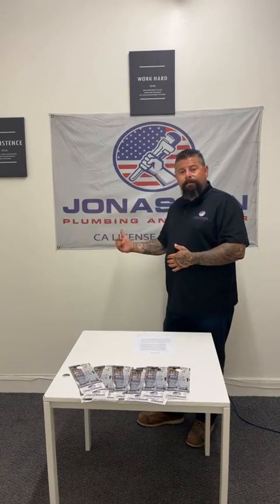So every 6 months we'll put you on a maintenance program, whether you have a conventional storage tank heater or a tankless water heater. For tankless water heaters, we'll pump in a descaling solution into the unit and run it for the manufacturer-recommended time. Then after running the descaling solution through the tankless water heater, we run fresh water through it to flush it out.